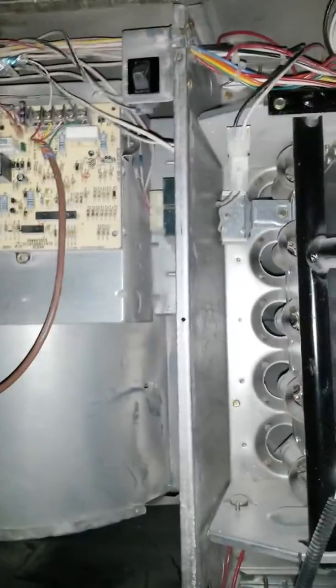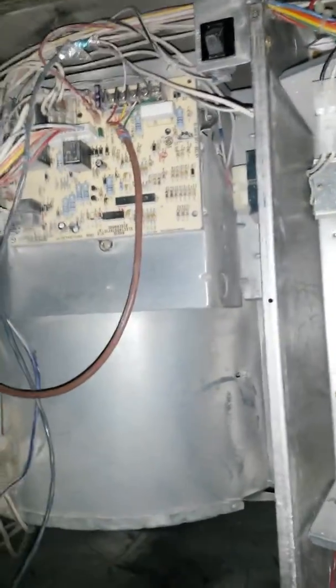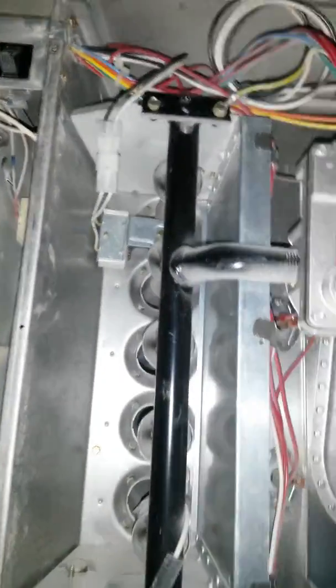I would suggest that we start looking at plans to put air conditioning downstairs in the basement to replace this system when it dies. I quite literally don't have any room to pull this blower assembly out of here because of the sprinkler piping on the other side. Not only that, but the beam directly above doesn't even let me pull motors out, so this unit is virtually completely unserviceable.